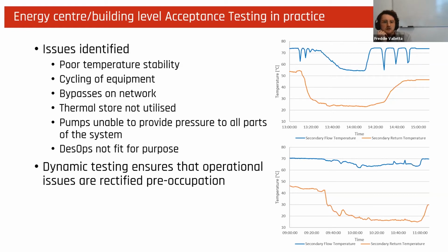In the load test on the first one, once this load was induced, the return temperature was dropping as we would expect as demand was induced on the system. However, the secondary flow temperature also drops drastically as well during this period. And then also, once this load was removed, the plate control caused several fluctuations in that return temperature, as can be seen in the dips in the blue line in the top right-hand corner.